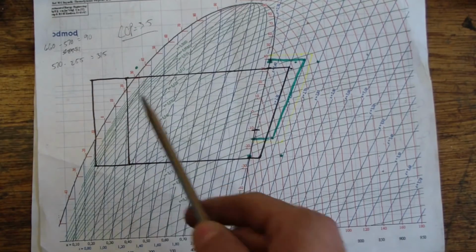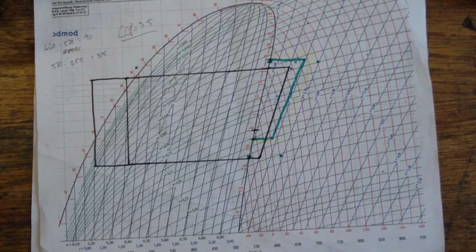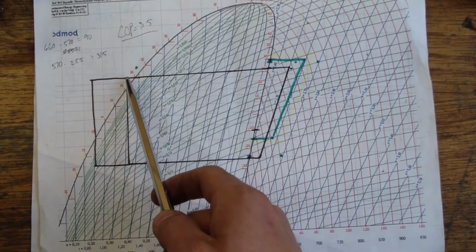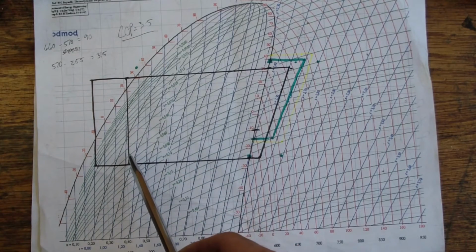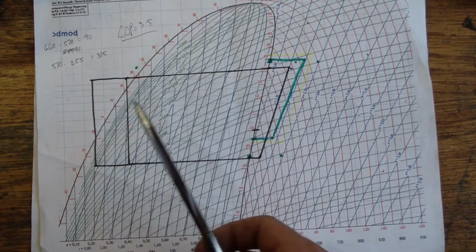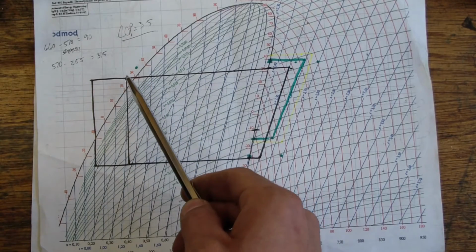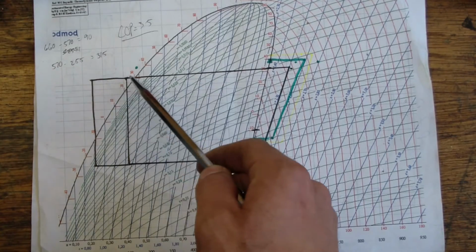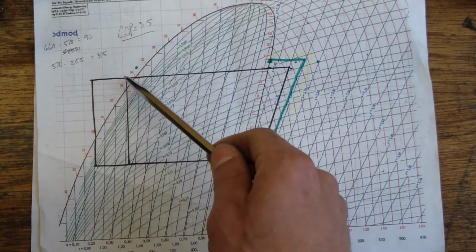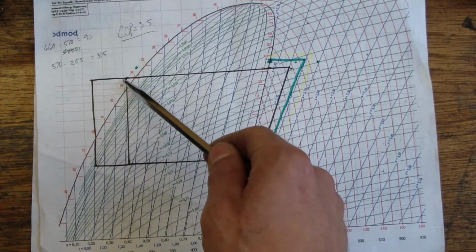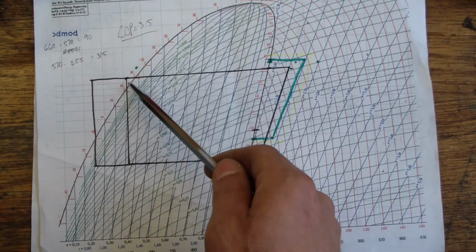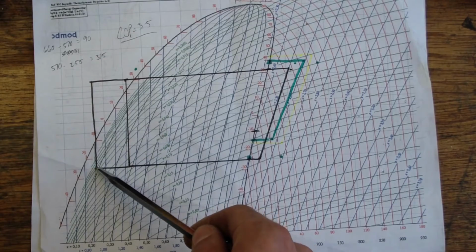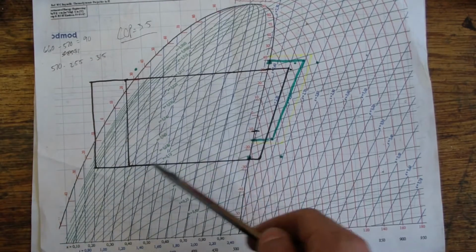What else can we talk about? Okay, the throttling device. One of the reasons that I have two vertical lines drawn here is because this one is essentially without a heat interchanger, and this one is. So because I have my capillary tube wrapped around my suction line, I'm able to more effectively subcool that refrigerant before it exits the capillary tube. So that's why I'm way over here in the subcooled region. This one's without the heat interchanger. So we've got a lot more flash, as you can see right there. So with the heat interchanger, I'm able to cool a lot more, a lot less flash gas, and I have more liquid in the evaporator doing cooling work.